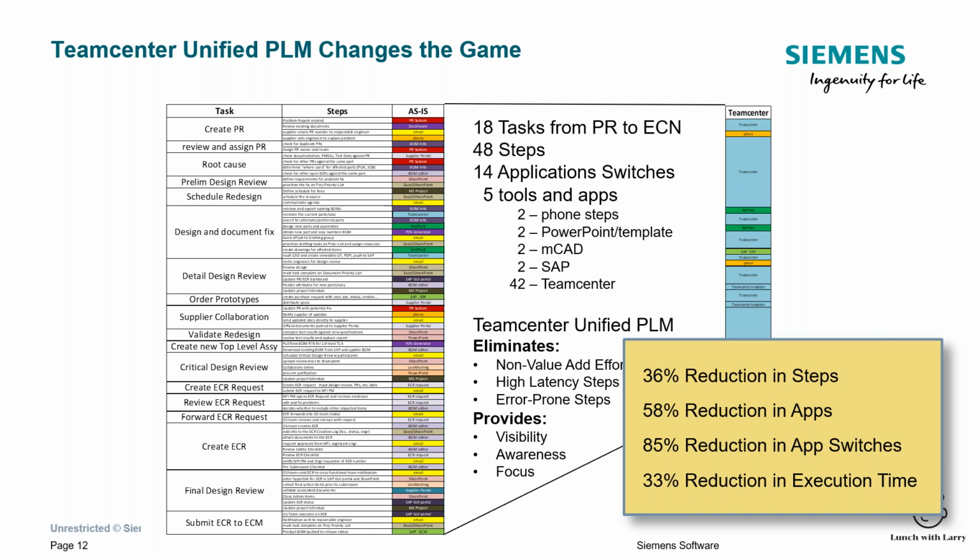So one of the considerations that we need to have is we're not just doing these processes, we're also pushing it through change management. As we author a design, we're going to have a certain amount of review. That review is going to get populated into a DHF. The DHF is going to go through a process maybe of a phase gate review, and we're going to do ECRs and ECNs. We're going to have approvals, right? So there's a variety of different systems that we're going to have to move our design through.